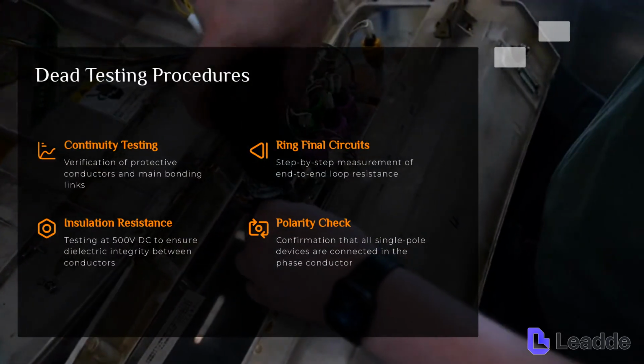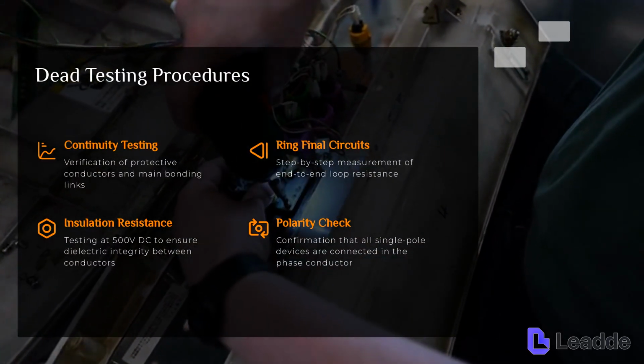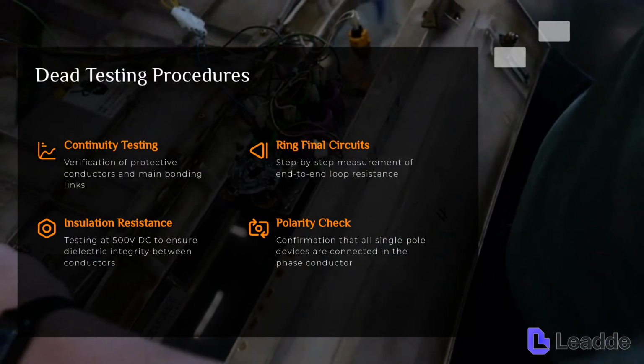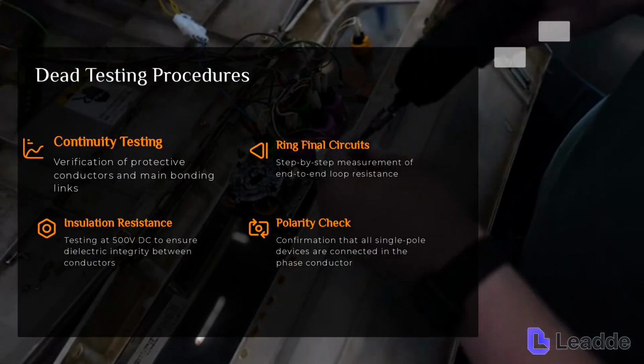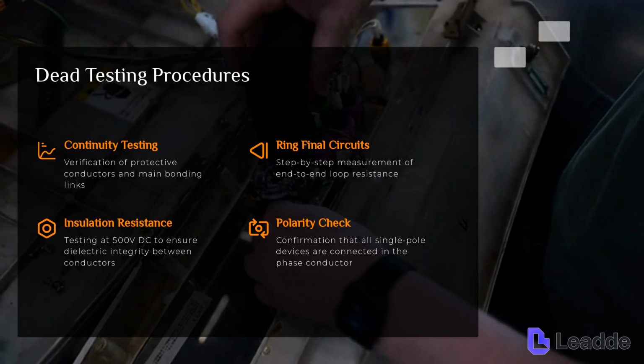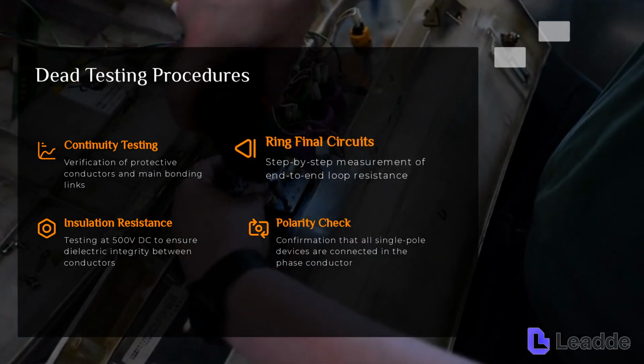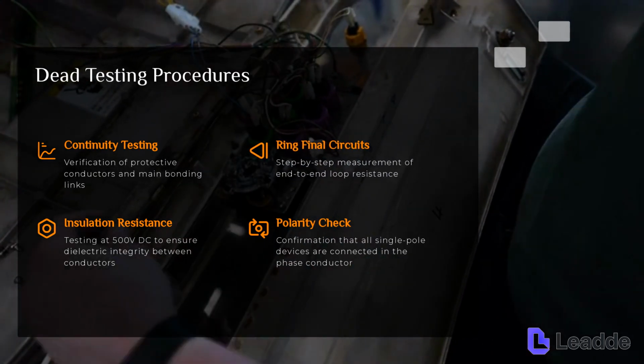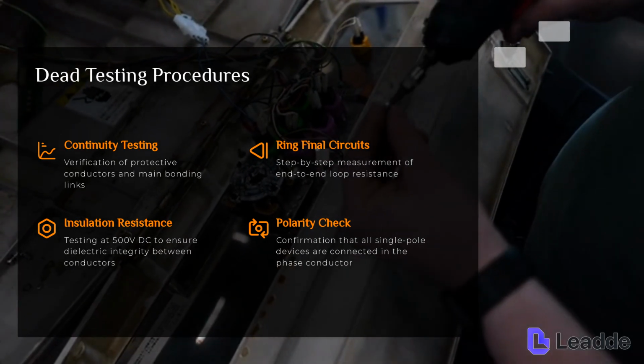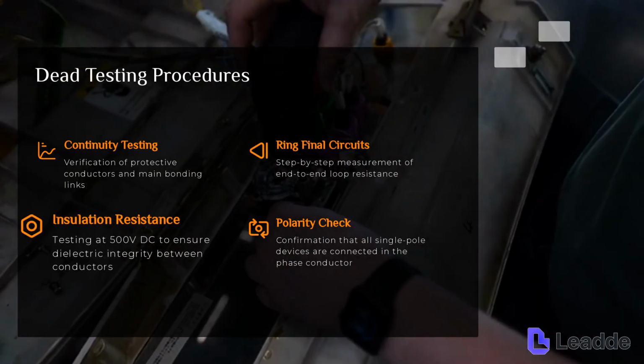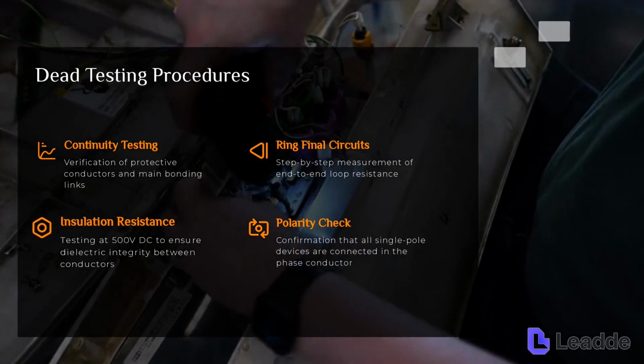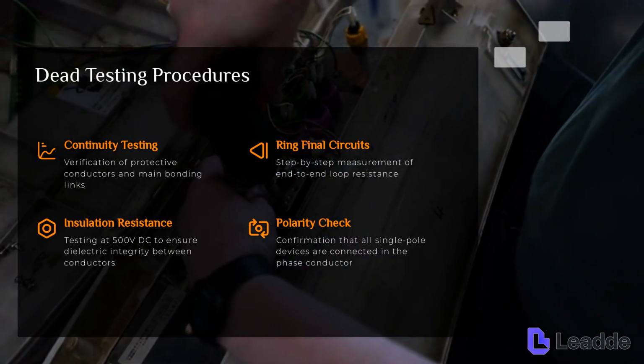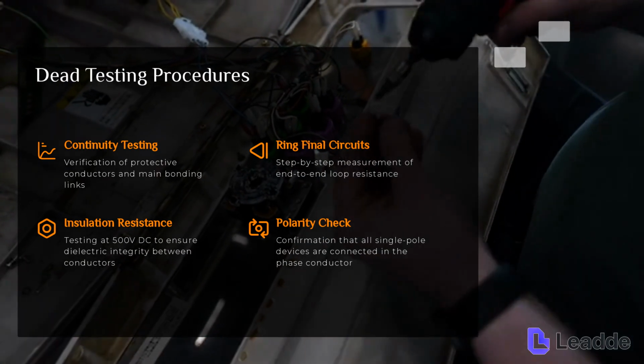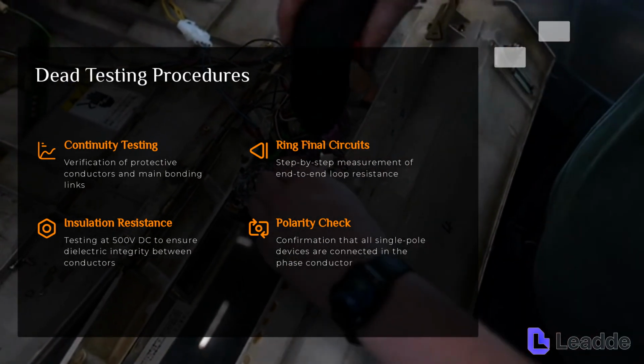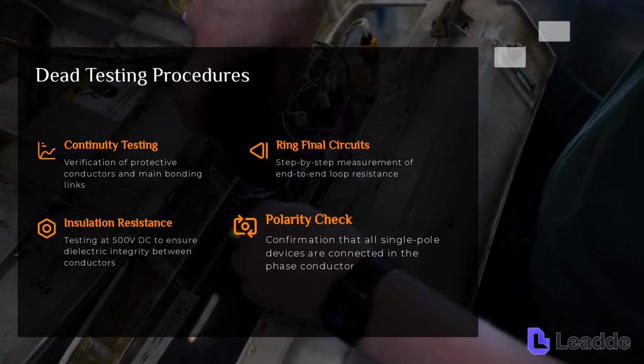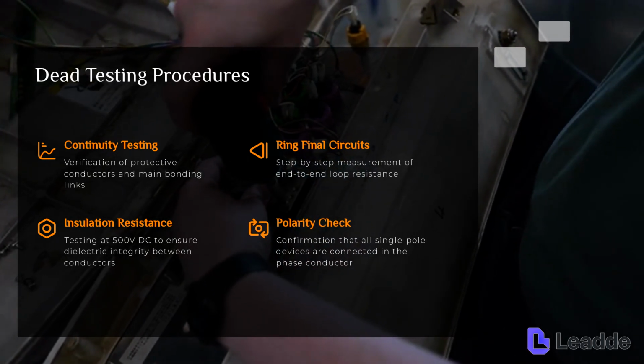Now, we will address dead testing procedures. This includes continuity testing to verify protective conductors and main bonding links. We will also cover step-by-step measurement of end-to-end loop resistance for ring final circuits. Furthermore, insulation resistance testing must be conducted at 500 volts DC to ensure dielectric integrity between conductors. Lastly, a polarity check is required to confirm that all single-pole devices are correctly connected within the phase conductor.